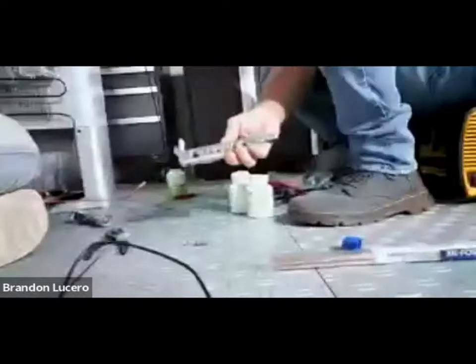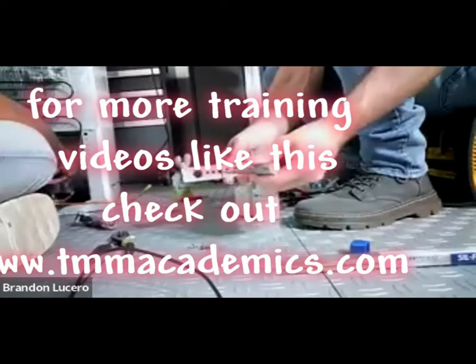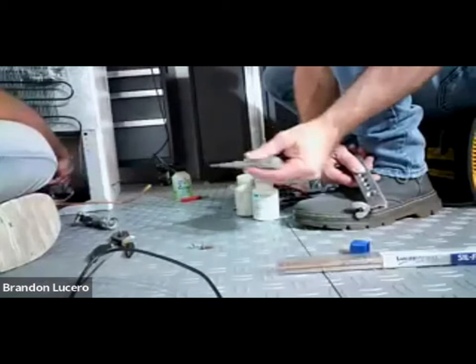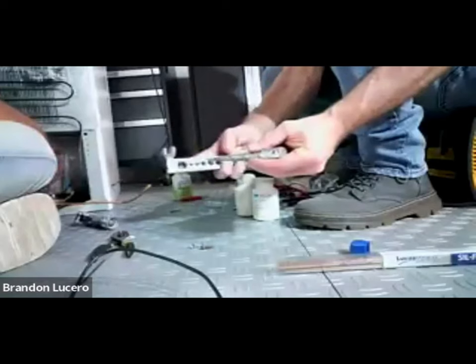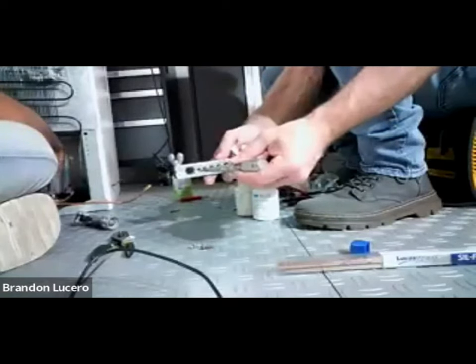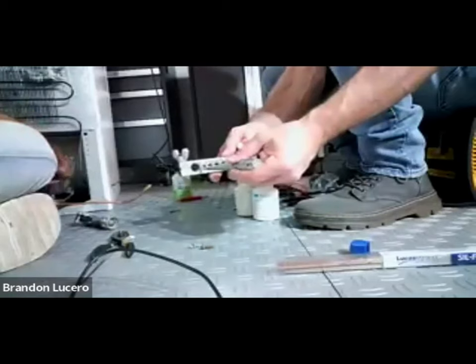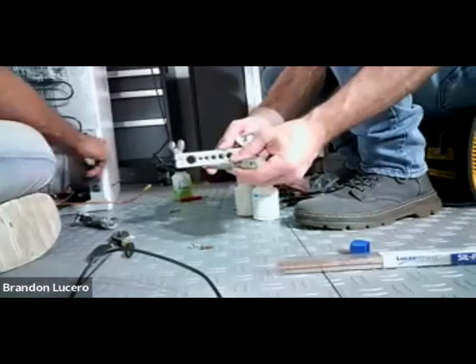Make sure you use the swaging block on the compressor before you try to use the swaging tool to open it up. If you just use the tool on the open pipe, you will crack it where it welds to the compressor and damage it - it'll either crack or bend the pipe. Put the swaging block against the compressor over the pipe, then use the swaging tool. But again, if it's got solder on it, it might not work too well.